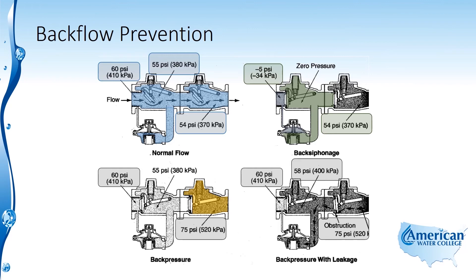The final situation is back pressure with leakage. You can see there's 75 psi on one side and 60 psi being supplied, and there's an obstruction in the check valve. Because the relief valve is open due to this difference in pressure, you'll see leakage dripping to the ground. This is an indication that there's a problem with this check valve assembly because there is leak by.